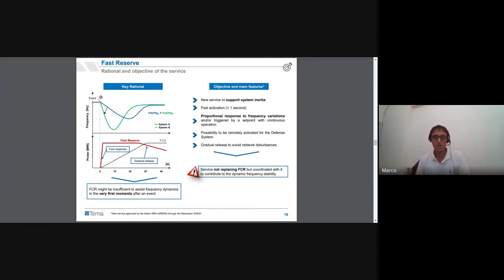Primary regulation has a long response time, because in our grid code it's defined as a regulation that completes full power within 30 seconds, with no limit or constraint on duration. Fast reserve, in contrast, is a specific regulation that has to react within 1 second and support the system in the hour when it has a very low level of inertia.